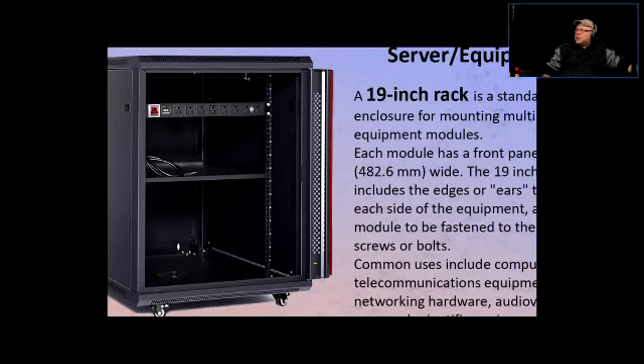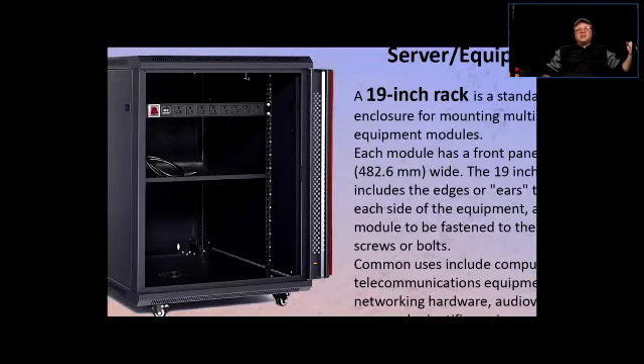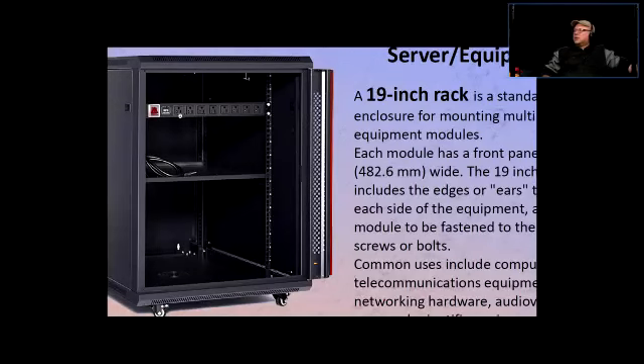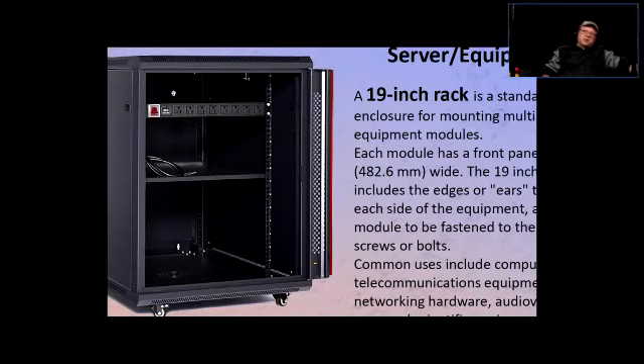If it's not a sequential PDU, you flip the switch and all power outlets come on at the same time. With a lot of equipment, that can cause a huge momentary overload — sometimes you don't want that. A sequential PDU means when you flip the switch, the outlets come on sequentially: this one comes on, maybe two seconds later that one, then another, and so on. There's no common draw from all equipment at once — it gradually powers up things. Some are programmable, some are not.